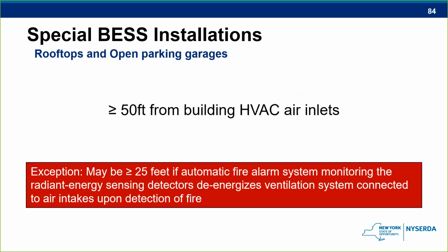Also, systems that are on rooftops or in parking garages need to be at least 50 feet from air intakes. There's an exception to reduce that distance to 25 feet if there's a way for the fire detection system to automatically deactivate the ventilation if there's an incident.